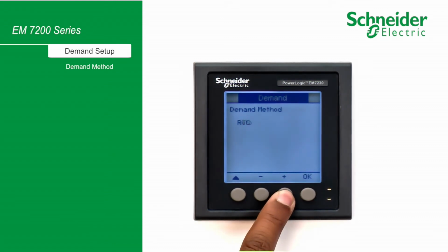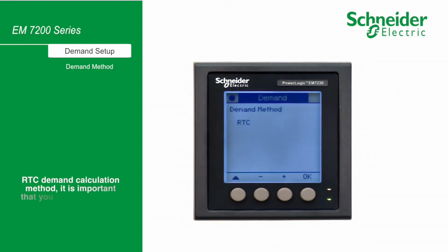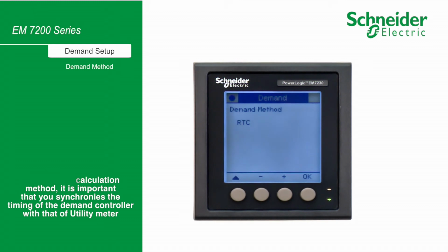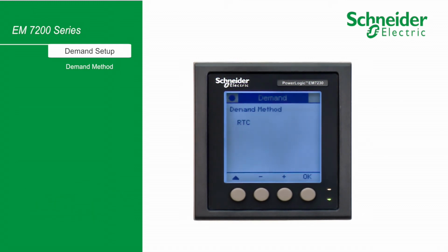It could be auto or sliding window type or user type or real-time clock, also called as fixed window type. For RTC demand calculation method, it is important that you synchronize the timing of the demand controller with that of utility meter. Let's select RTC.